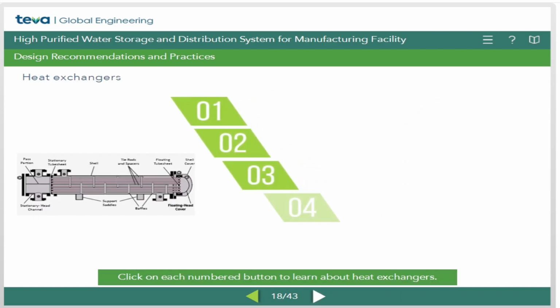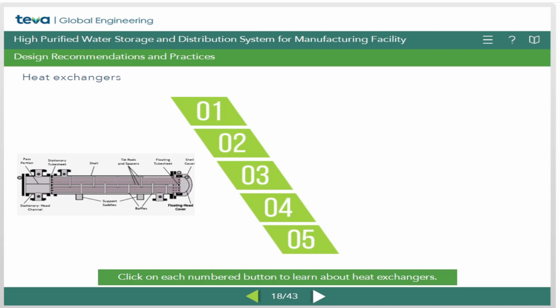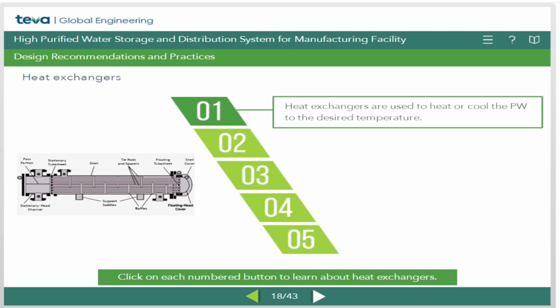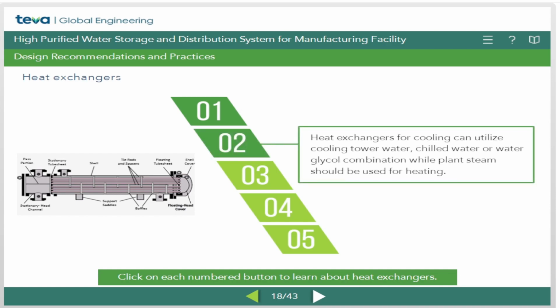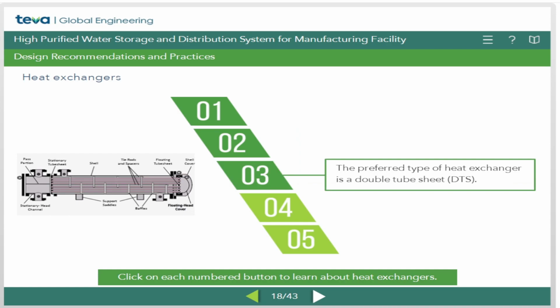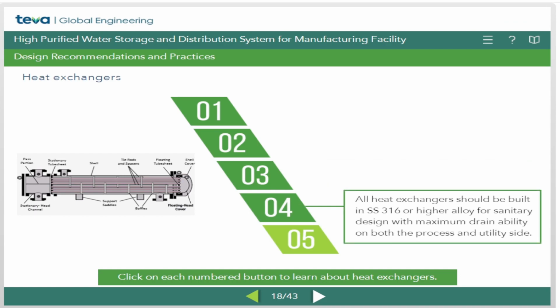To learn about heat exchangers, click on each numbered button. Heat exchangers are used to heat or cool the purified water to the desired temperature. Heat exchangers for cooling can utilize cooling tower water, chilled water, or water glycol combination, while plant steam should be used for heating. The preferred type of heat exchanger is a double tube sheet. All heat exchangers should be built in SS316 or higher alloy for sanitary design with maximum drain ability on both the process and utility side.